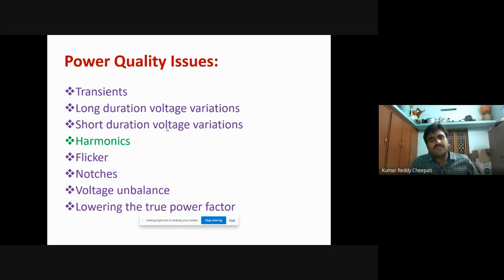When it comes to long duration voltage variations, they are again of three types: over voltage, under voltage, and sustained interruption. Over voltage is when the voltage envelope is more than 1 per unit for a duration of more than 1 minute. Under voltage means the reduction of voltage amplitude for a duration of more than 1 minute. Sustained interruption means that if the voltage or current amplitude is zero for a duration of more than 1 minute, that is termed sustained interruption. All these long duration voltage variations are due to equipment failure or intentional outage.